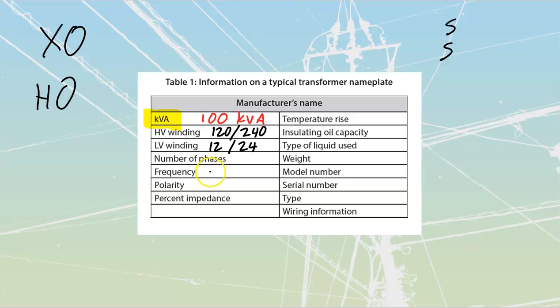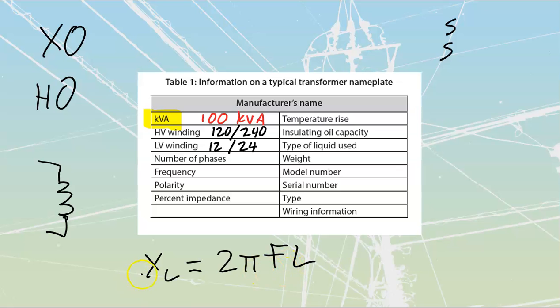Frequency does have to be rated on there. Once again, if I change the frequency of any component, say I've got a 50 hertz transformer and I put it onto 60 hertz, there's going to be a difference. Why? Because that transformer winding is an inductor, and we know that XL is equal to 2 pi FL. So if I had a transformer with a certain XL based upon it being 50 hertz, and then I upped that to 60 hertz, the frequency value would be increasing, which would mean the XL value of that transformer would be increasing, which would mean that I could carry less amps.